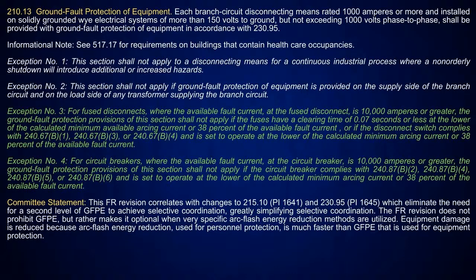The service. Or you could provide it at the feeder that was over there. So once you have it in one spot, you don't need it at another. Now, one of the things that I like here is that it's talking about the available fault current. This is where they're telling you that you have 10,000 amps or greater, and that the ground fault protection provisions they have set up shall not apply if the fuses have a clearing time of 0.07 seconds or less.